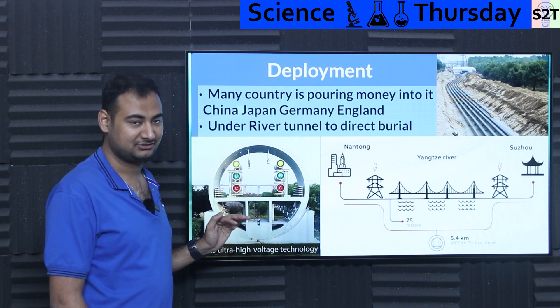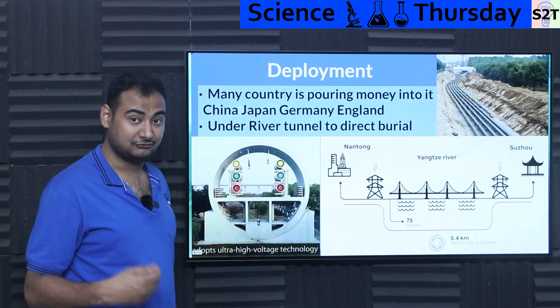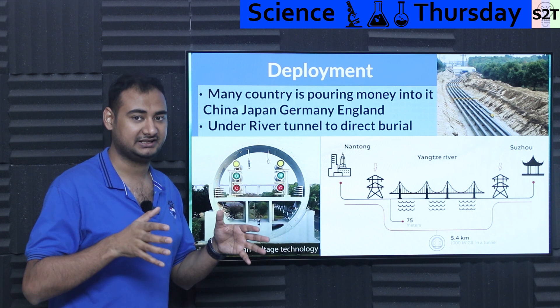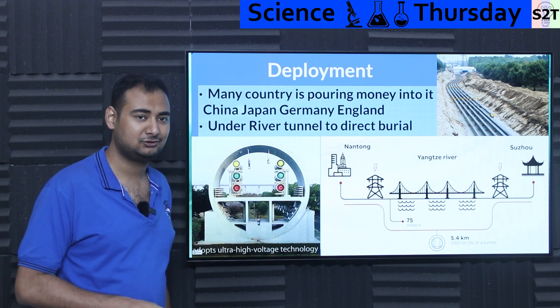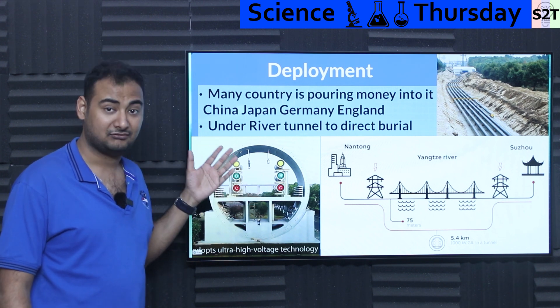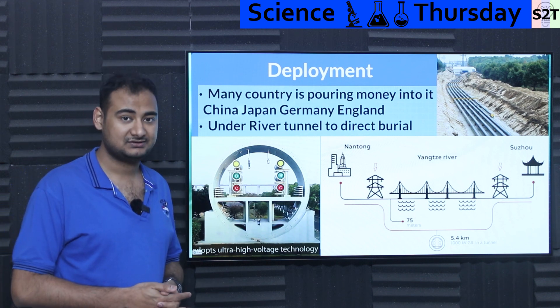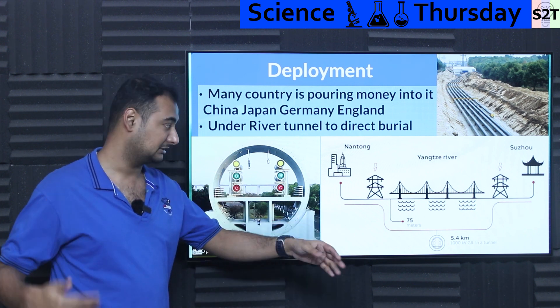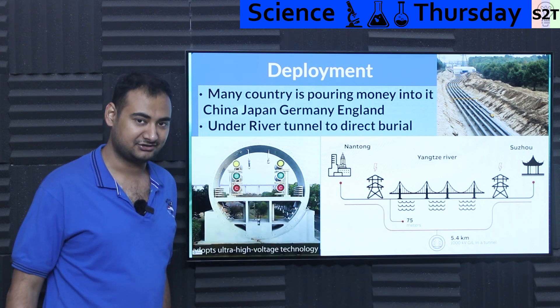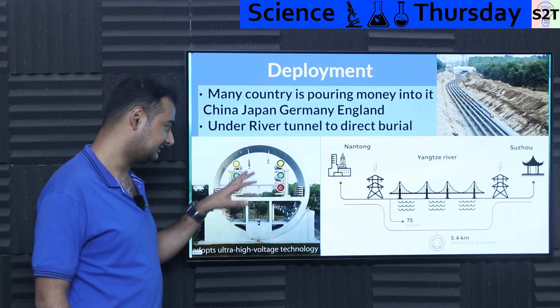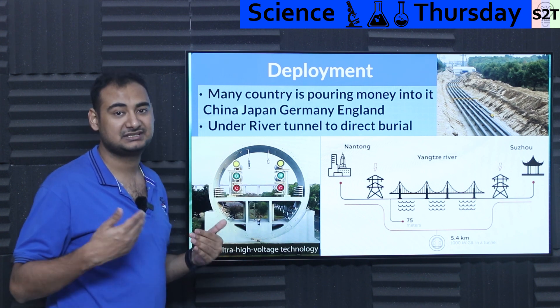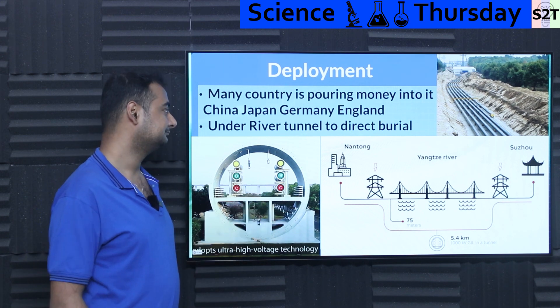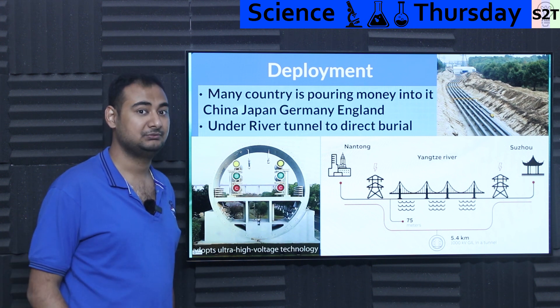It's a boatload of power — bonkers amount. It's about 75 meters deep and the voltage rating is 1,000 kV. There are other systems going to 1,200 kV but only at small scale. Why did China choose GIL over HVDC? It was cheaper. HVDC also requires converter stations that are even more expensive. For a short hop of six to seven kilometers, it's unwise to build an HVDC converter station. So they went with AC using GIL, avoiding the capacitance losses that would occur with normal conductors. A lot of countries are investing in this — there may be one near you that you haven't noticed.